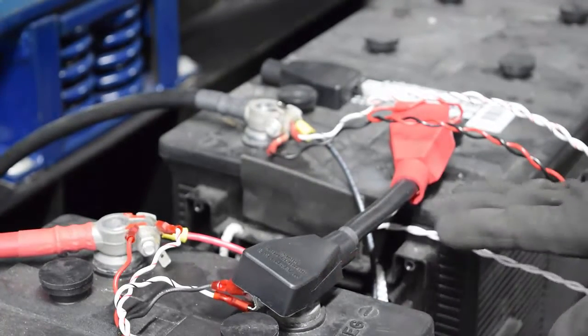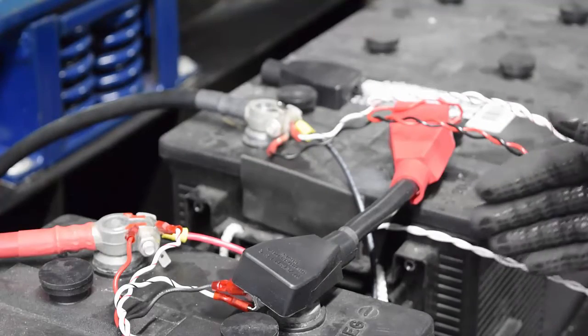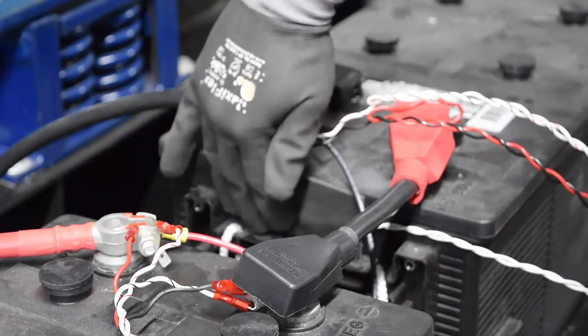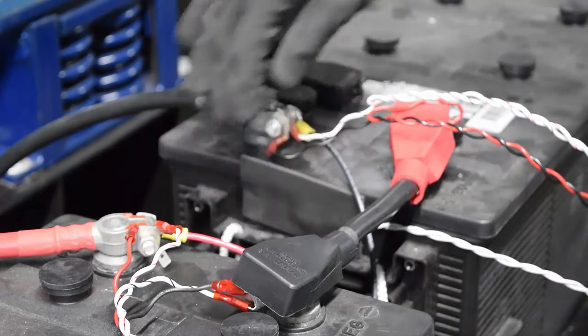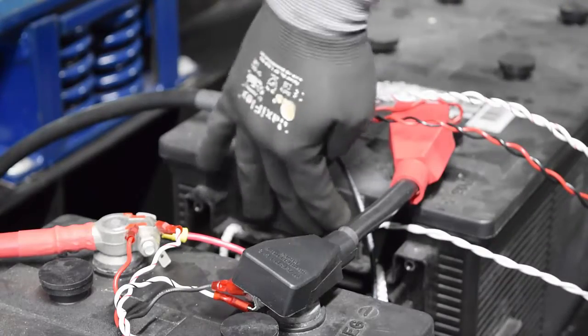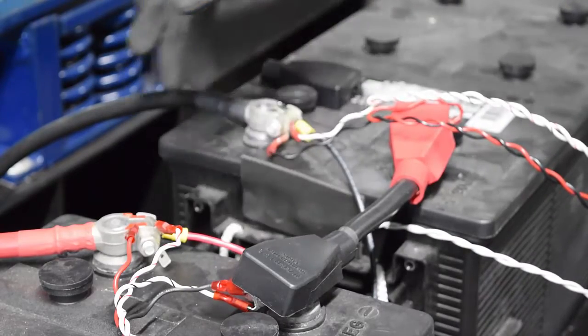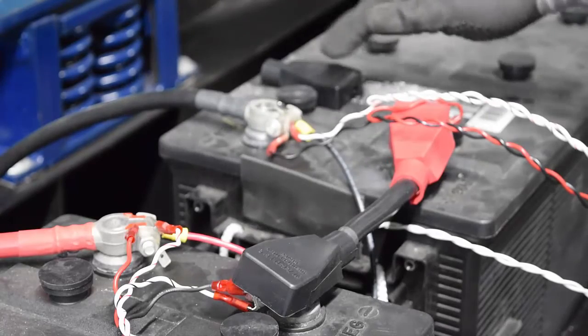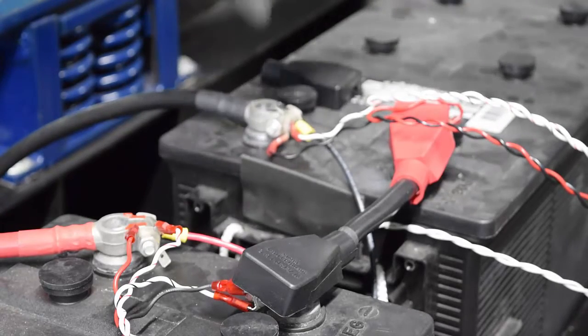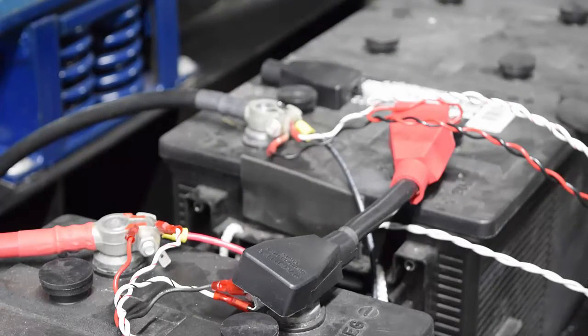So what we did in this instance, because there's so much space between the batteries, I flattened the foam pad out and placed the sensor right underneath. So it's insulated from moving air and it's pressed up against the battery pretty close to the terminals and getting a pretty good temperature reading.